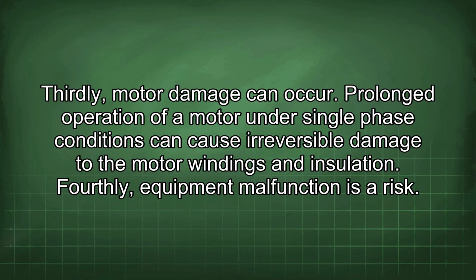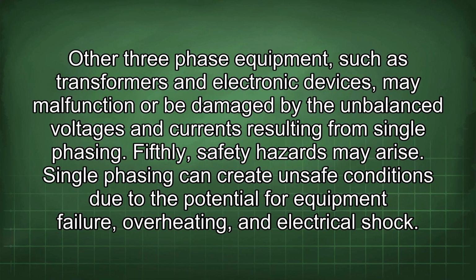Fourthly, equipment malfunction is a risk. Other three-phase equipment, such as transformers and electronic devices, may malfunction or be damaged by the unbalanced voltages and currents resulting from single phasing. Fifthly, safety hazards may arise. Single phasing can create unsafe conditions due to the potential for equipment failure, overheating, and electrical shock.